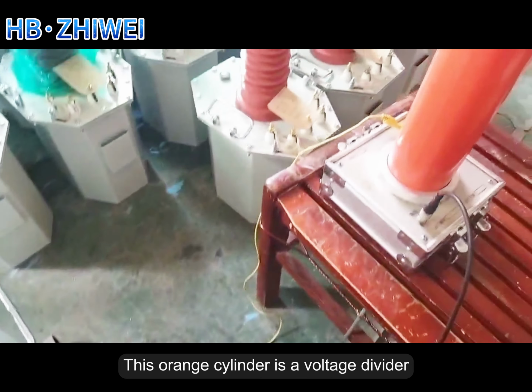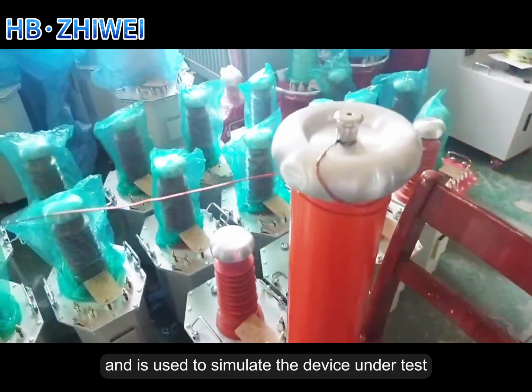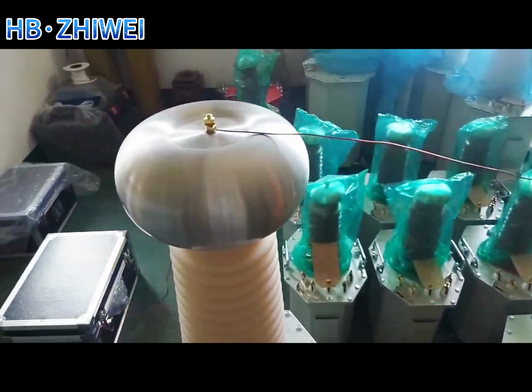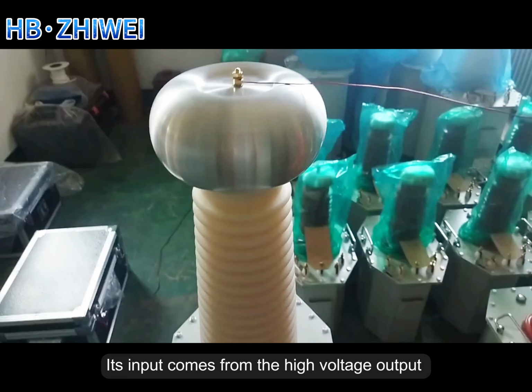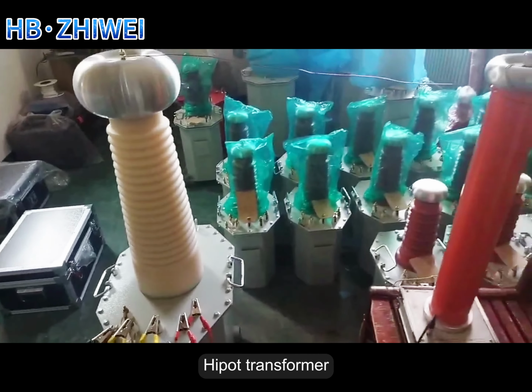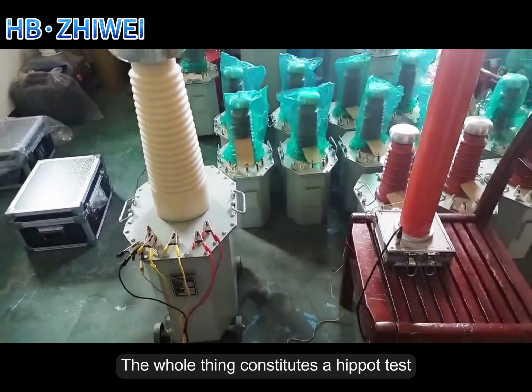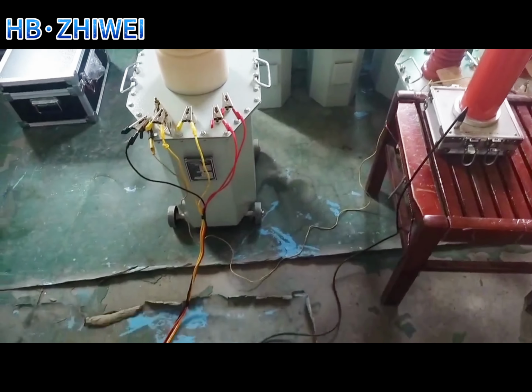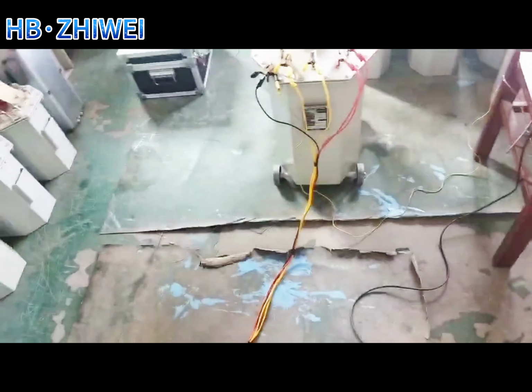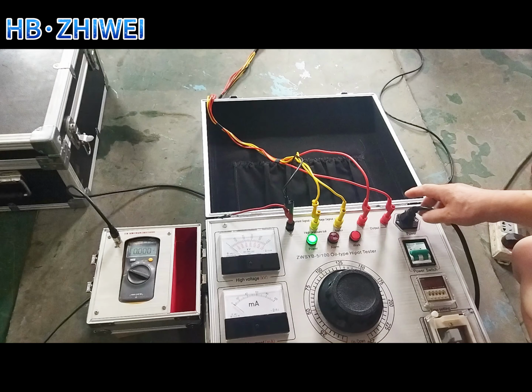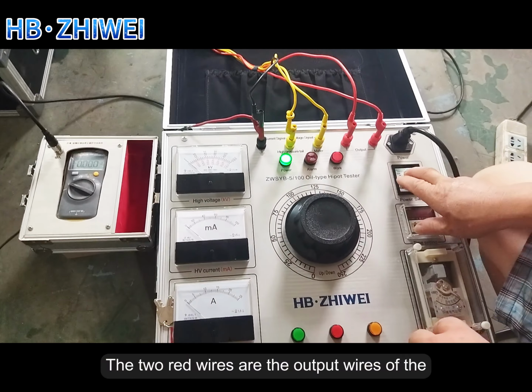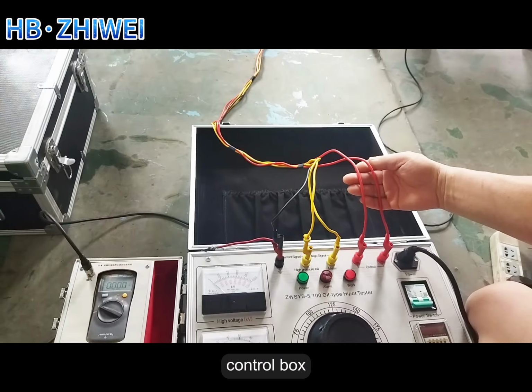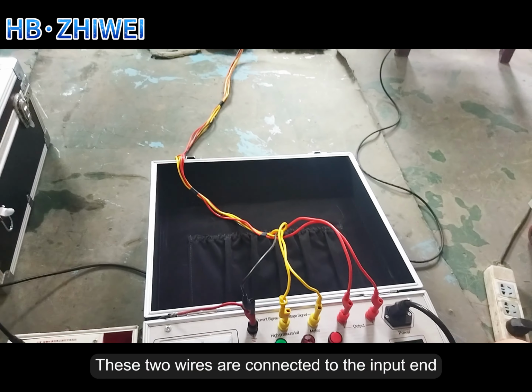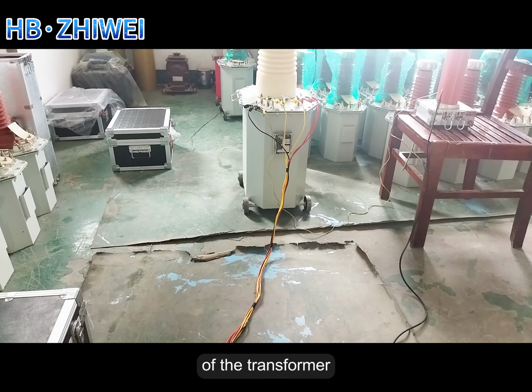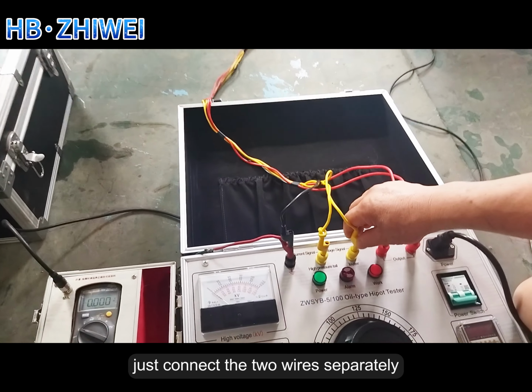This orange cylinder is a voltage divider and is used to simulate the device under test. Its input comes from the high voltage output at the top of the Hipot transformer. The whole thing constitutes a Hipot test. The two red wires are the output wires of the control box. These two wires are connected to the input end of the transformer. Just connect the two wires separately.